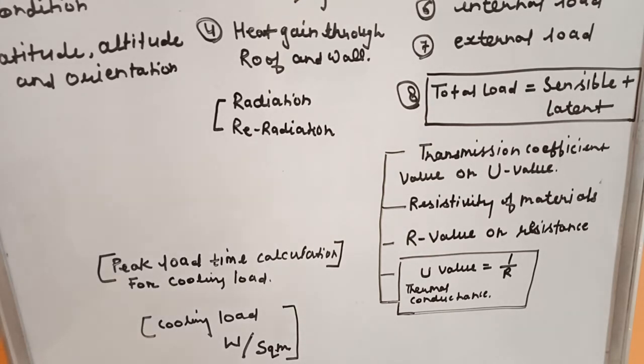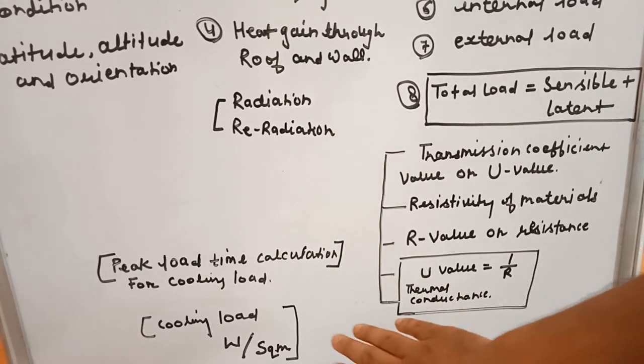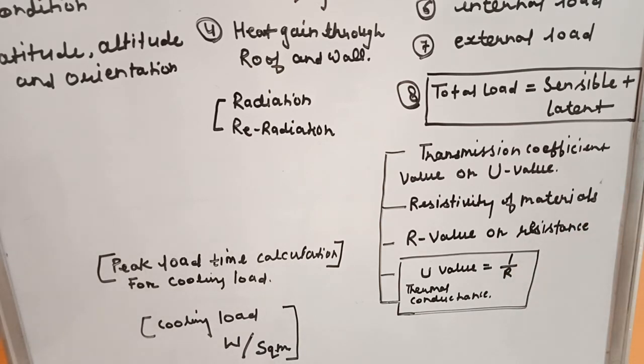So we learn about the heat, temperature difference, and different types of heats like latent heat, sensible heat, then it becomes total load, and area of facade, and depending on U value and R value. So we calculate the load calculation process, and it is calculated at a peak load time. So whenever the peak load in building, that time only we calculate all the related load like inside, outside, external, internal, and all the load by occupancy and by the machinery and heat loss as well. Then we get the actual cooling load. Okay, and it varies sometimes to the climatic zones. Then we are able to give this cooling load process to our design.